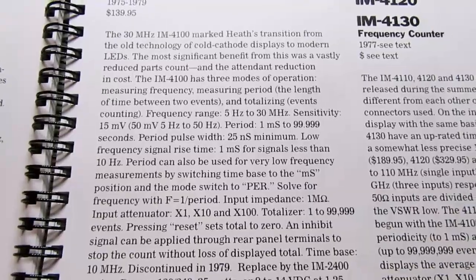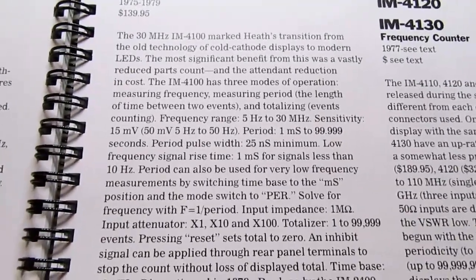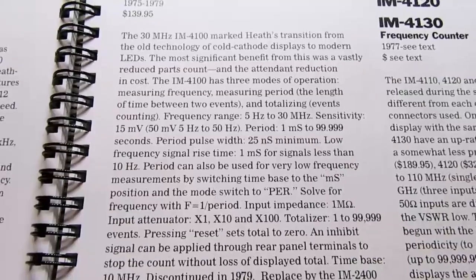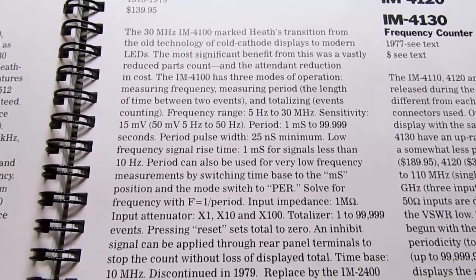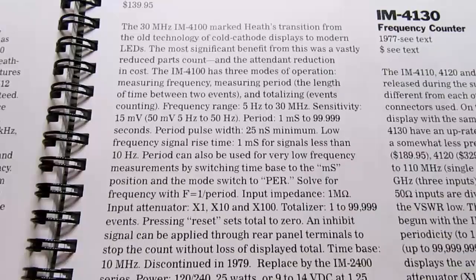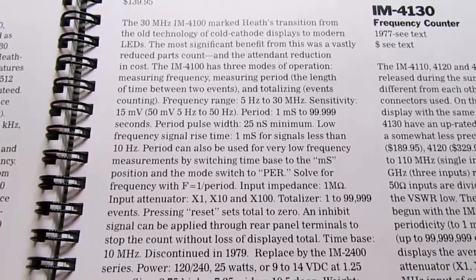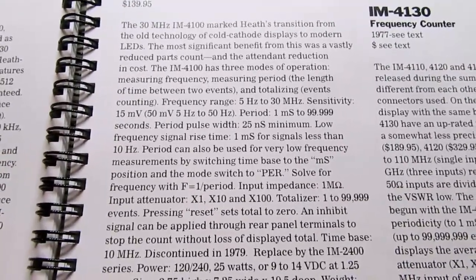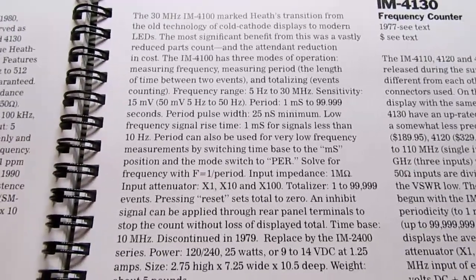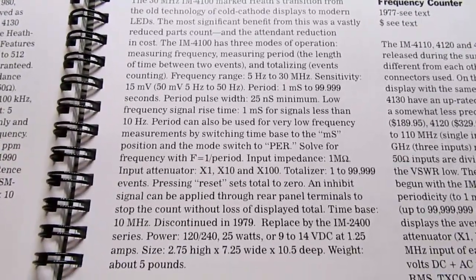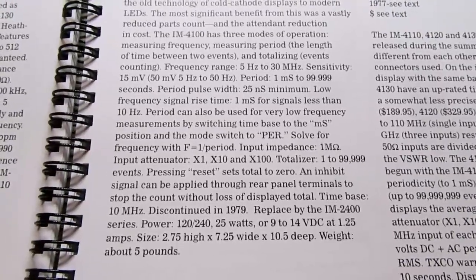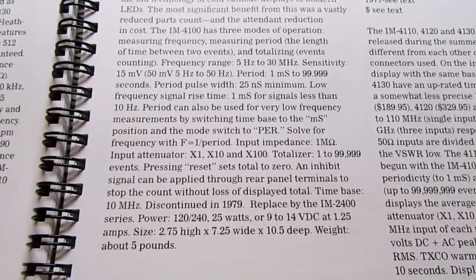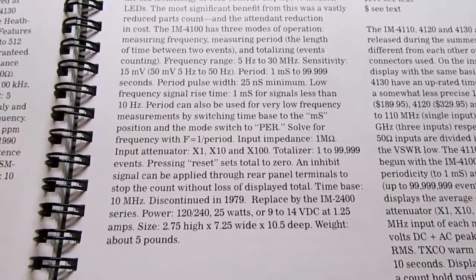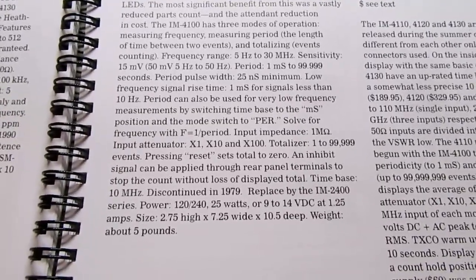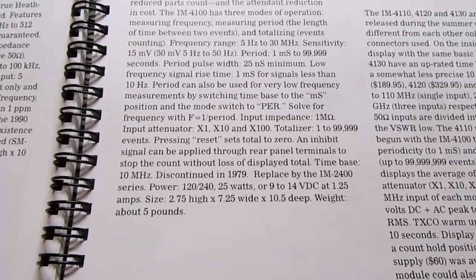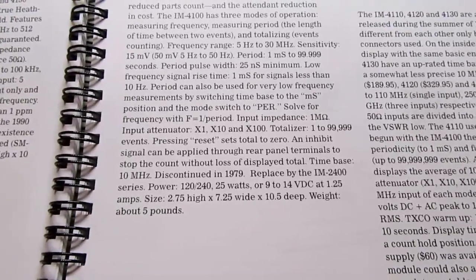Frequency range from 5 Hz up to 30 megahertz. The sensitivity is 15 millivolts, so it can register any input from that level on up. The period can be measured from 1 millisecond to 99.999 seconds. Low frequency, blah blah blah. The period can also be used for very low frequency measurements by switching the time base to the MS position and the mode switch to period. You have to manually solve for frequency using the formula.